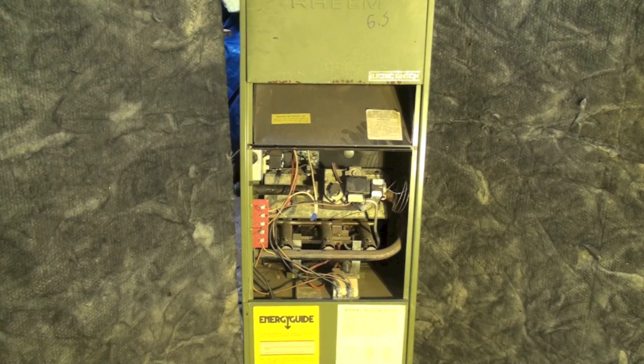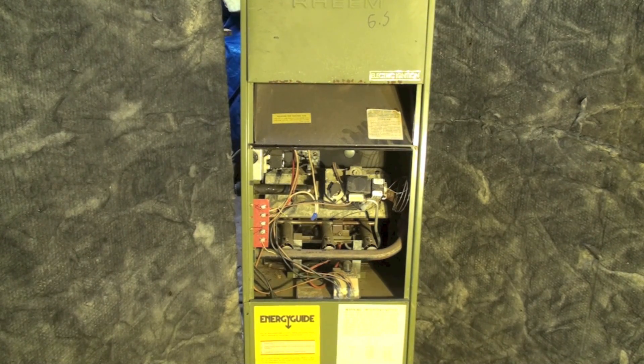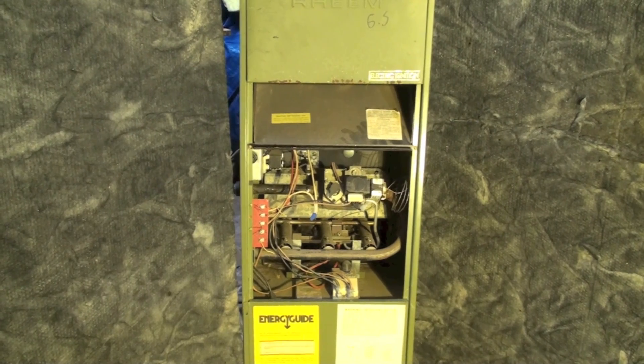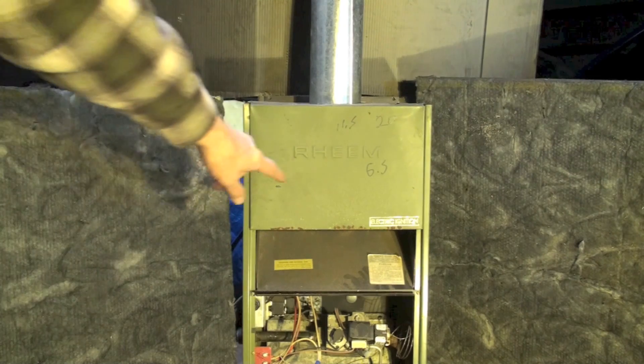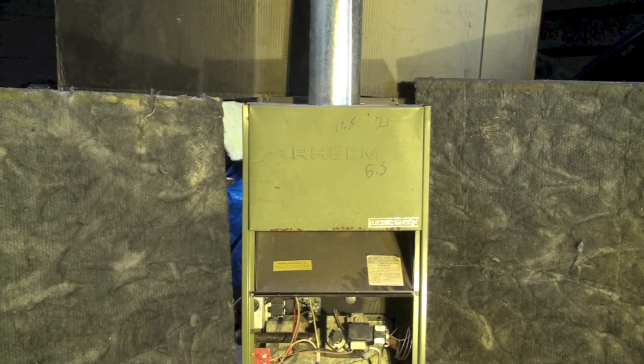This furnace is a Rheem RGDA, which was a fairly long model series with a lot of different furnaces in it. This one is a little bit interesting because of the type of pilot and gas valve control it has. This is an old draft hood style — you can see the draft hood right here — an 80% furnace probably built in the mid-80s.